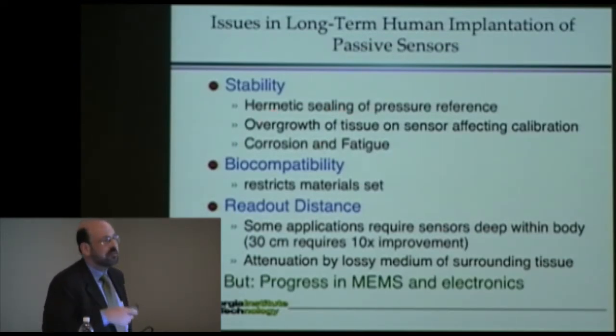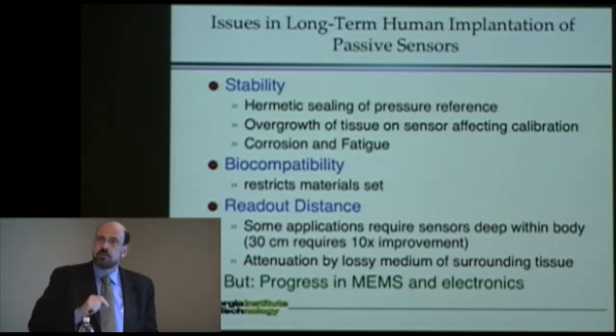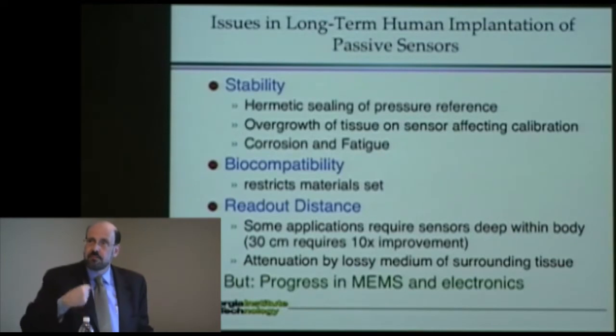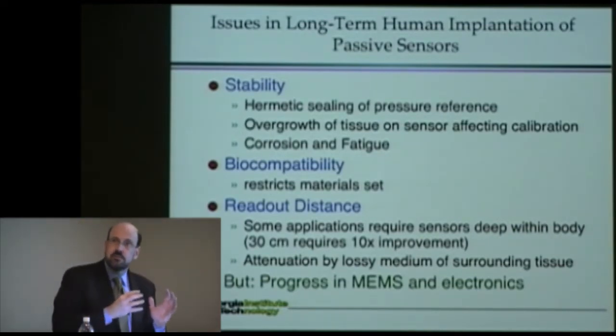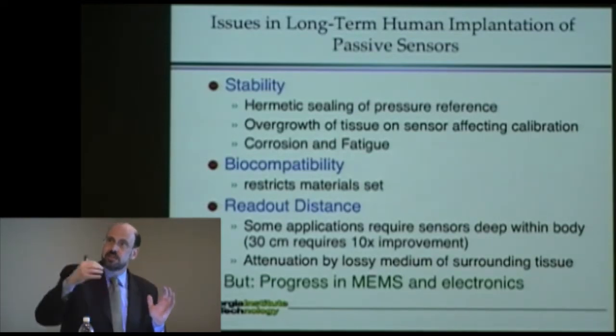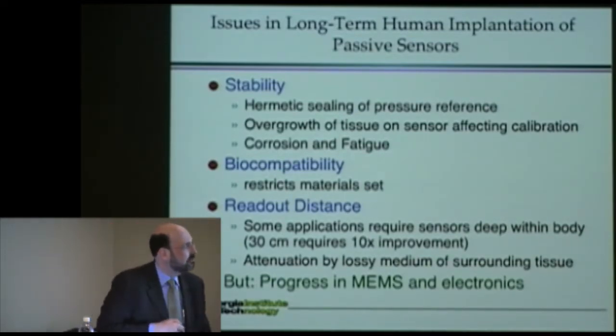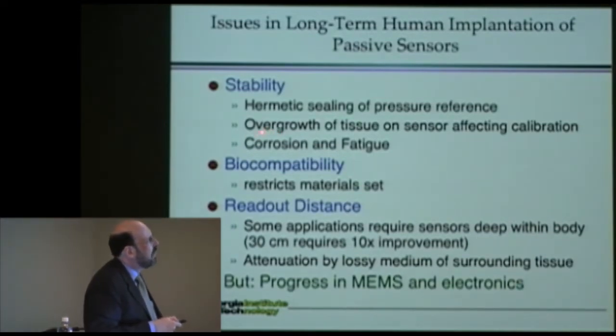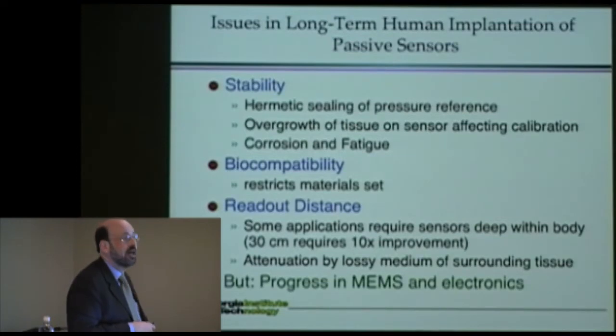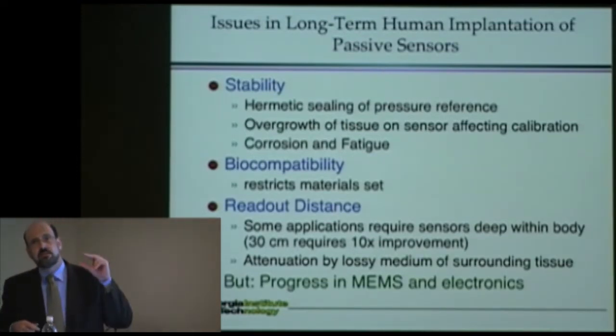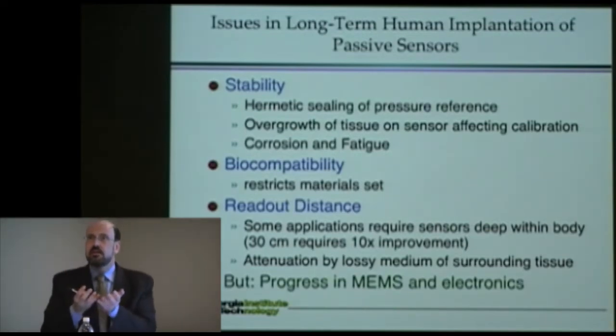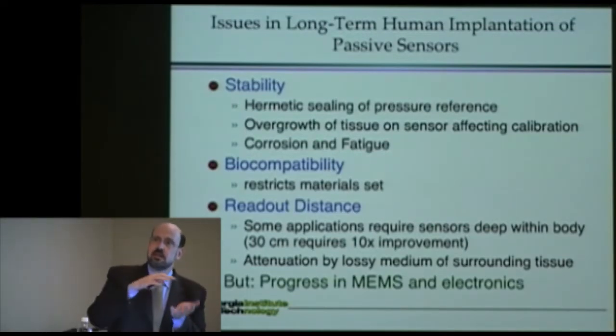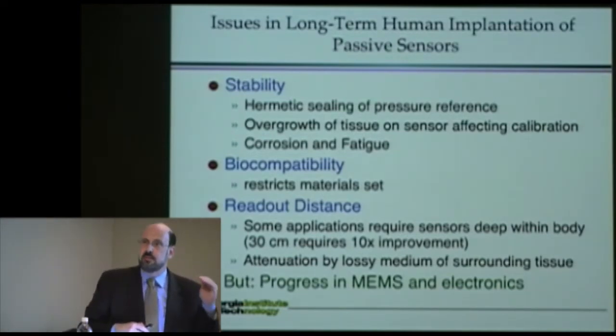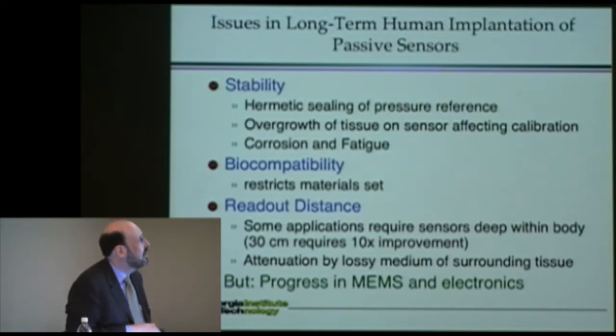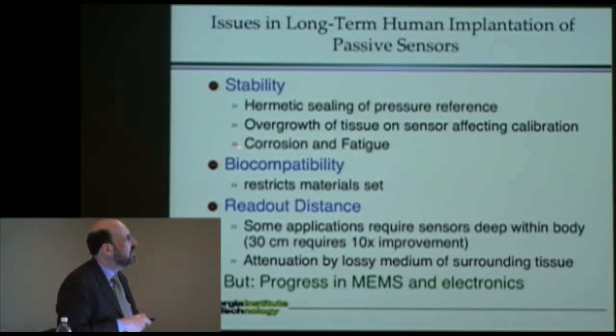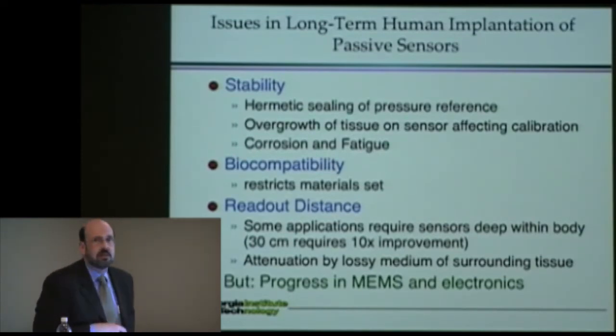What if the pressure reference, that cavity inside, changes pressure because of molecular leakage in and out? Obviously, heat shrunk plastic is probably not going to be able to withstand molecular penetration over a decade time period. So we have to make sure that it's hermetically sealed. We have to worry a little bit about overgrowing tissue on the sensor, affecting its calibration. If we have a sensor that's relatively flexible and the body grows tissue on the outside, we have to make sure that tissue doesn't affect the overall calibration of the sensor. So that sets a maximum limitation on how flexible we can make the device. And then we have to worry about corrosion and fatigue in this chemically harsh and moisture-filled environment.